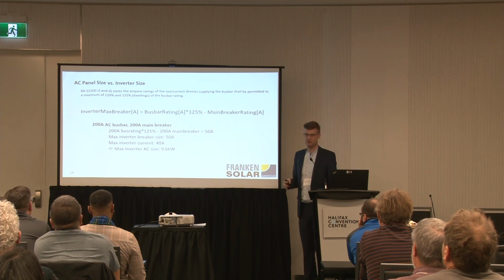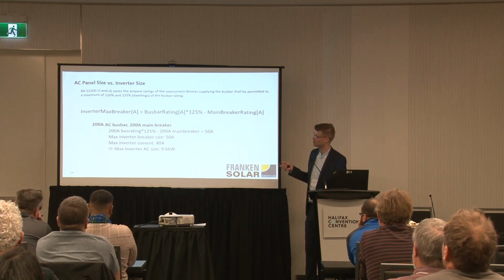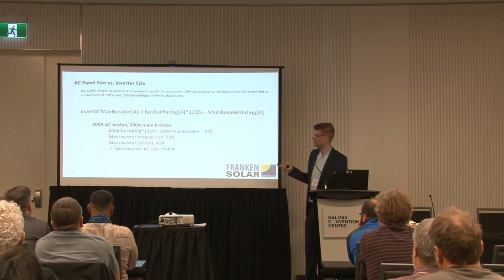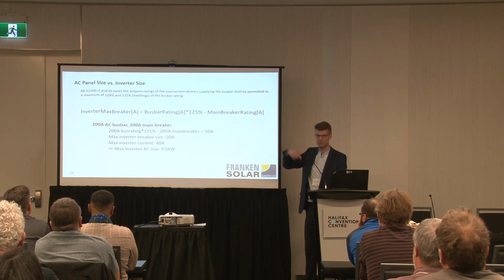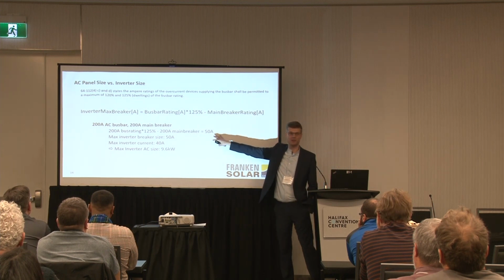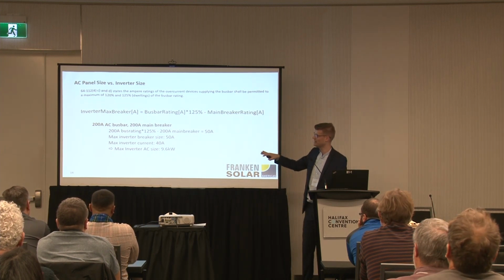Let's do a quick example for the most common electrical system in Canada. It's a 200 amp service, which has a 200 amp busbar. It has a 200 amp main breaker, and if we do the math, 200 times 1.25 is 250. We subtract the 200 amps that are already coming from the grid. So you have 50 amps available as the breaker size according to 64-112.